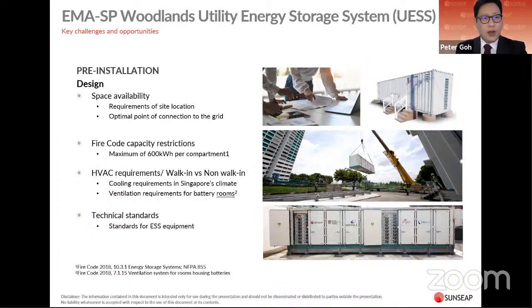Next, on to ventilation. Our current fire code requires battery rooms to have ventilation. The keyword here is 'rooms,' meaning people can walk into the battery container—it's treated like a room where people can work and enter. We had this initial design, but we then changed it to a non-walk-in design, where the doors are located along the entire length of the container and the racks can be accessed from outside. We feel this is much safer, and I think it will also be more preferred by the authorities compared to the walk-in version.